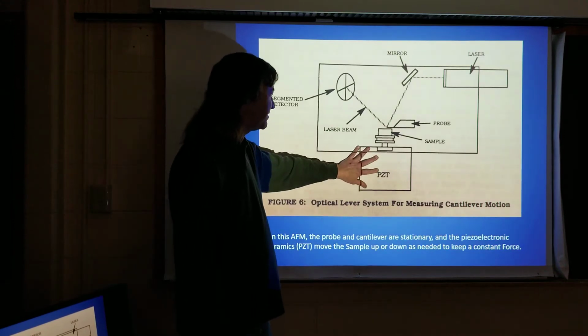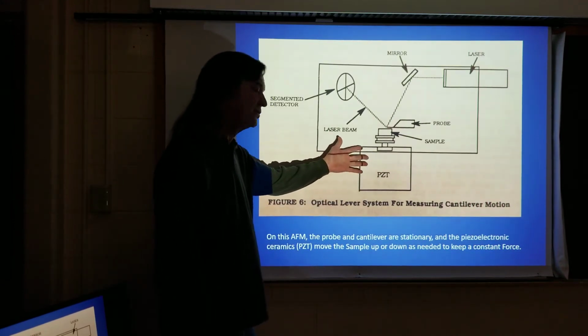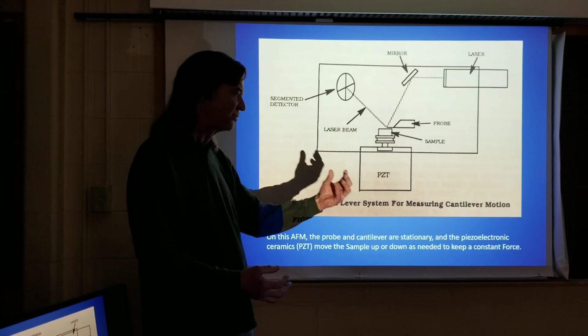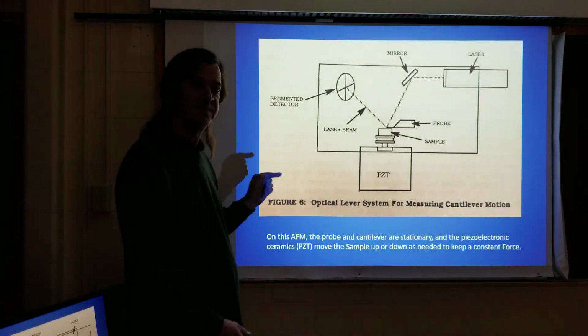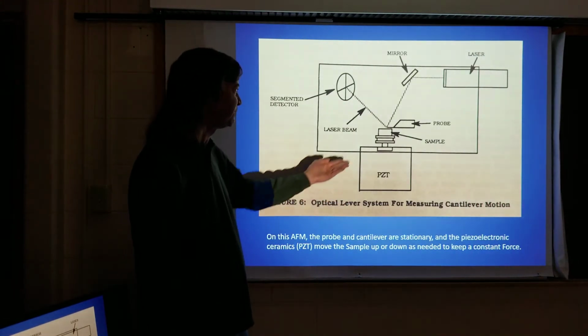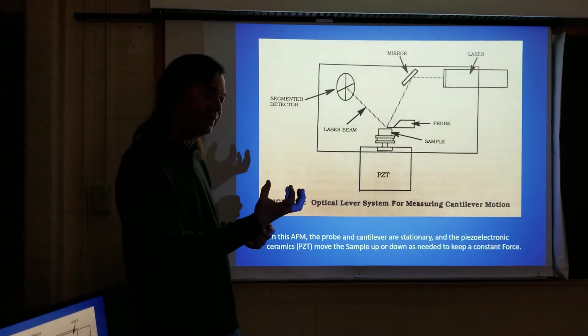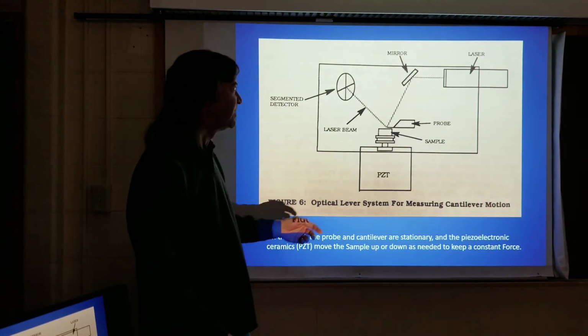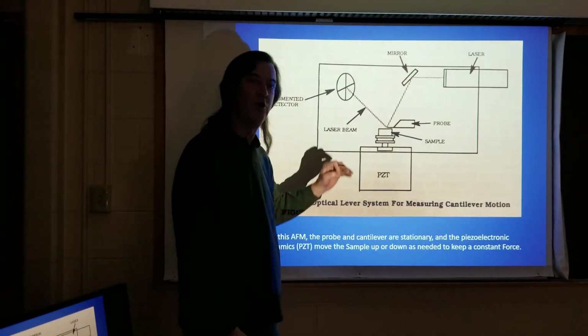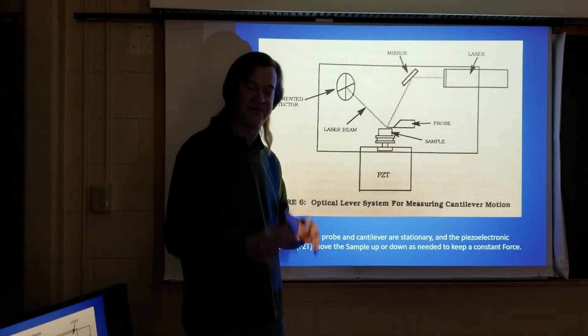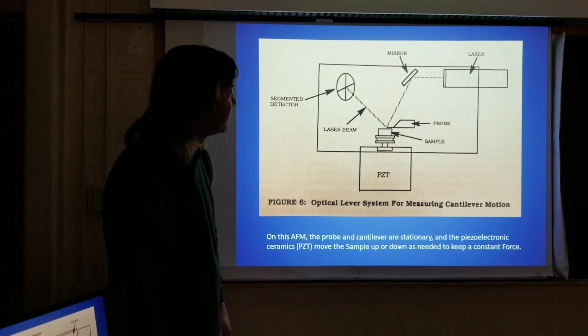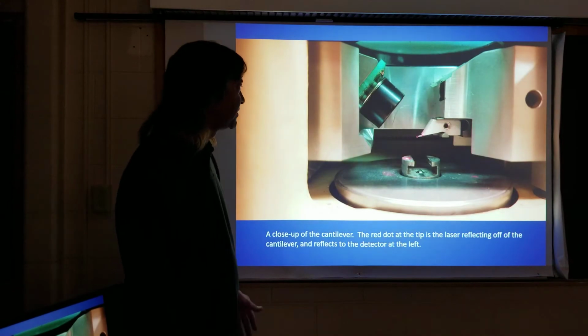And then again, we have piezo electronics here. These work just like the STM ones. The STM ones were actually on the tip, where the tip was. This one actually is right on part of the sample. So the sample in this case is going to move around. That way the laser and the probe can be at the exact same spot for the entire time, with no movement on those.